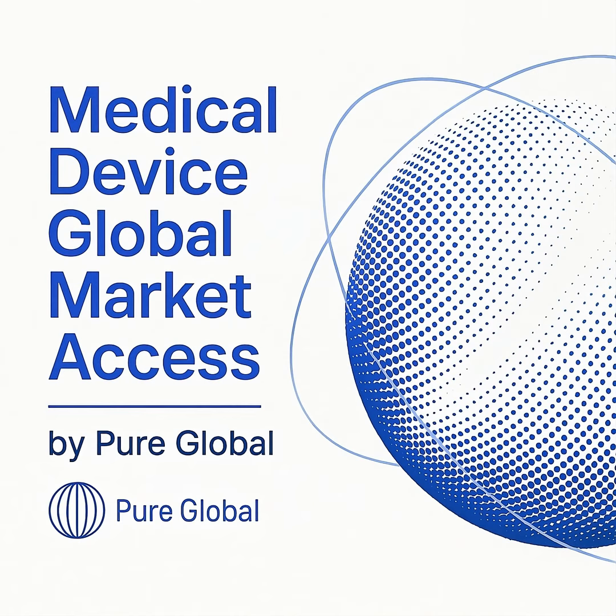Supply chain controls, essential for marketing safe medical devices, are often seen as burdensome. They require defining responsibilities and meeting them, often involving regulatory and legal experts to embed requirements in supply or quality agreements. The EU's regulatory framework, updated in 2017 for medical devices, MDR, and IVDs, IVDR, aims to protect patients, ensure a smooth internal market, and create a robust conformity assessment system.